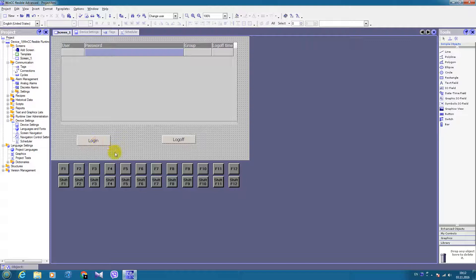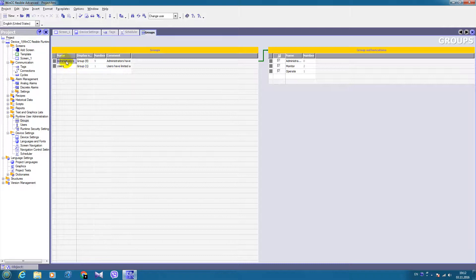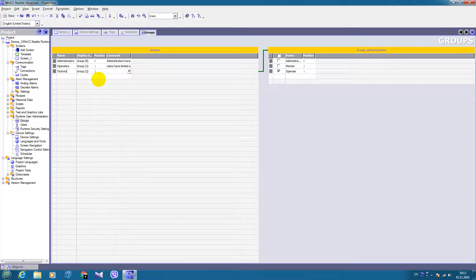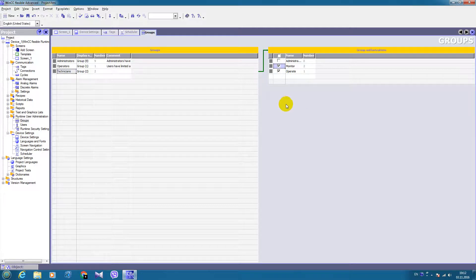So let's create user groups and users. We will do this in the runtime user administration folder. By default we have administrators; I will also add operators and, for example, technicians. Here you can see the authorizations that each group gets. Administrators can do everything; operators can operate; technicians can operate and monitor. That's how you can limit the access to different functions of the project.